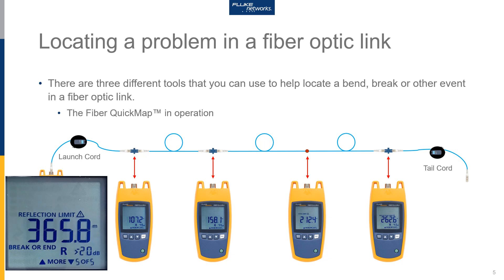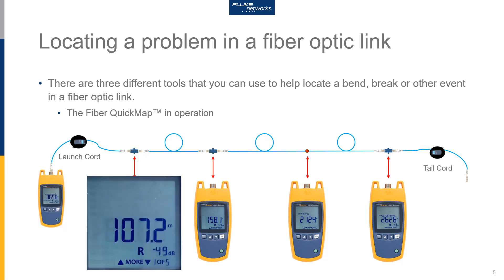Moving along the fiber from the launch point, this is where our launch cord connects to the fiber under test at 107 meters. The R value of minus 49 dB is the reflectance — this is a reflective event. Reflective events indicate that this is most likely a connector. So we have our first connector at 107 meters from the instrument, and this is the first of five events.